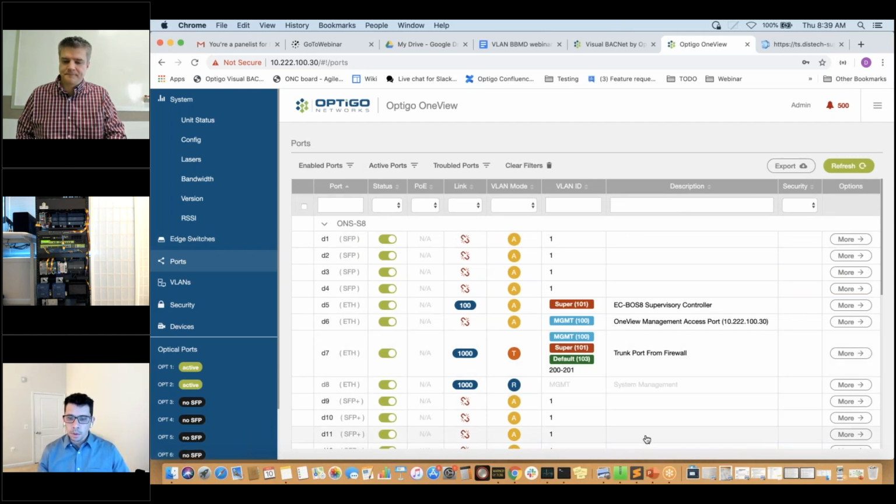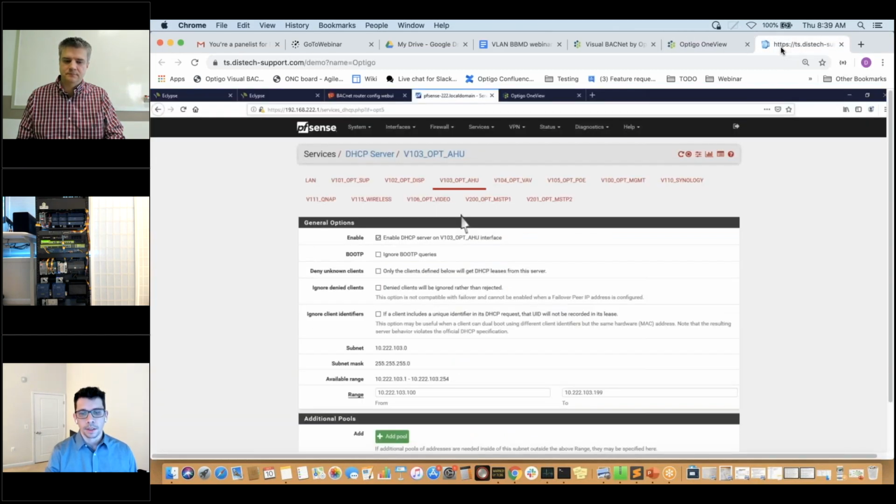But with the newer setups and a lot of IP devices, it becomes easier, especially at integration time, to have these MSTP devices able to talk at the IP level. And so it's creating some problems because the old way of having, say, two MSTP trunks and just throwing in a BBMD so that those two can talk, worked well at that level, but it does not scale well at all. So we have a couple devices here that we're going to demonstrate why that's not a good idea. And we're going to add a little bit of traffic for you to see it.